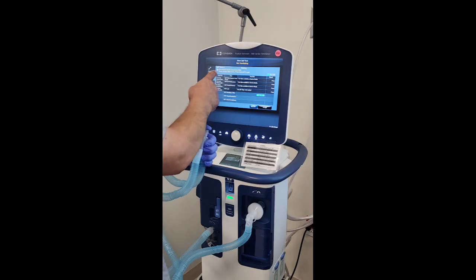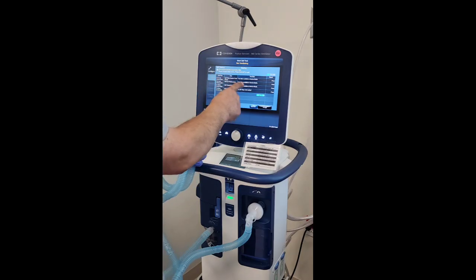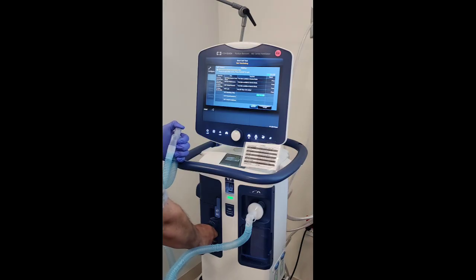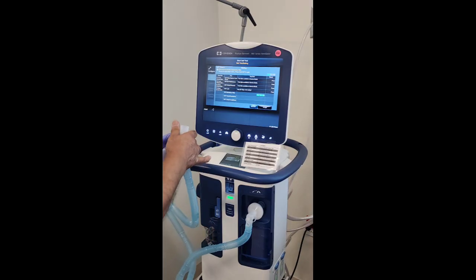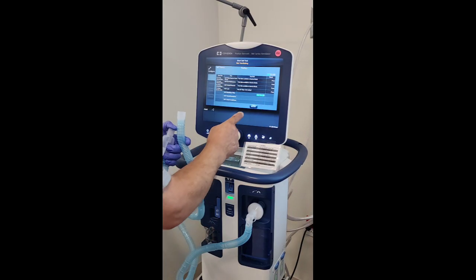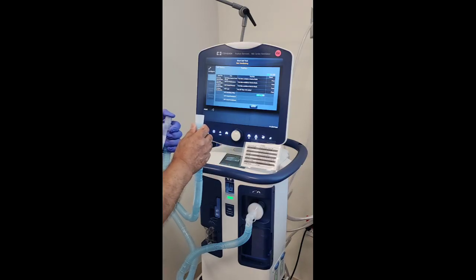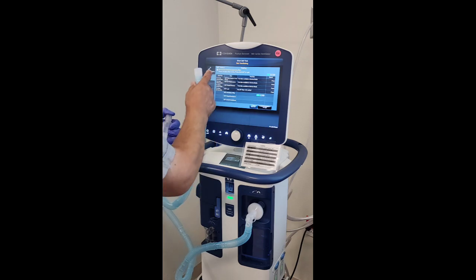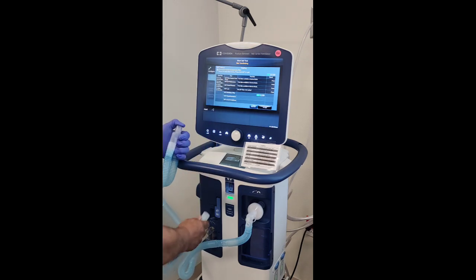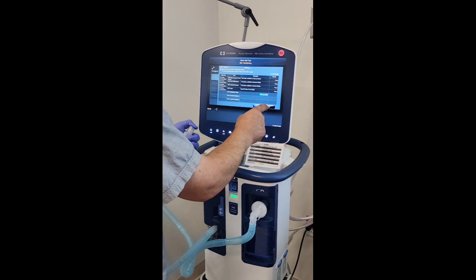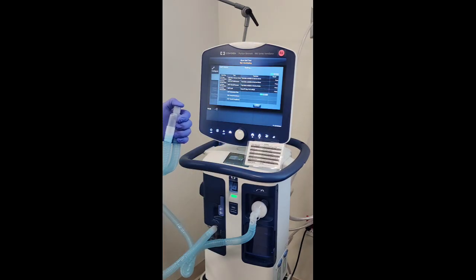Oh, it actually says disconnect circuit and expiratory filter. Right down here. I'm disconnecting this, and then I'm going to click accept. Okay, keep them both open. And now it says reconnect circuit and expiratory filter and accept. So I'm going to do that. Still have the Y blocked right now. And that passed. And now it's going to do circuit resistance and then compliance.